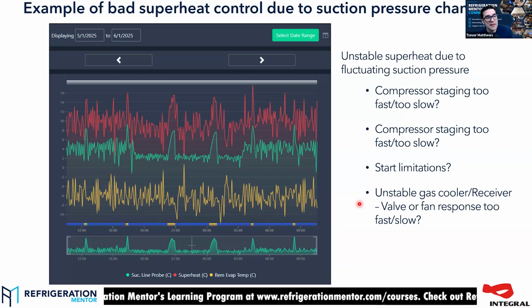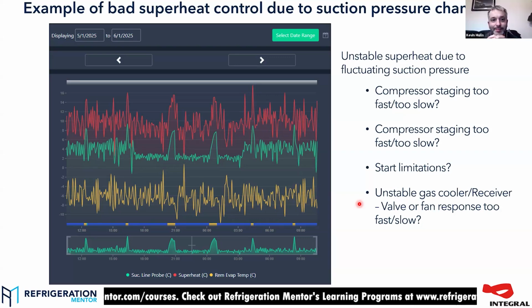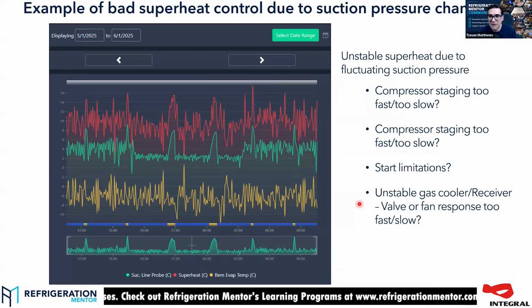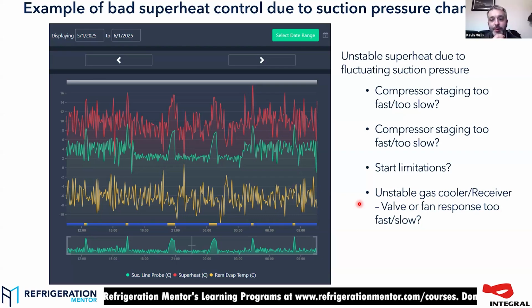And they're running the flash tank, I think he told me it goes down to 610 or 620 PSI. That's really low. I'm like, what are you running your flash tank at? And they're like 550. So we're looking at 40 bar or 42 bar at your gas cooler, and then all of a sudden you're running a 38 bar flash tank. You've got no pressure differential. The CO₂ is going to be like, why would I come into that horrible warm environment in there when I could sit in the nice warm environment on the gas cooler? You've got to give it some incentive to come in, because otherwise it's going to be like, I'm staying in the cold. And that does happen. Some systems cope better with that lower head pressure, but generally speaking, you've got to keep it above what you expect the flash tank to be at by some degree to make sure it keeps moving.